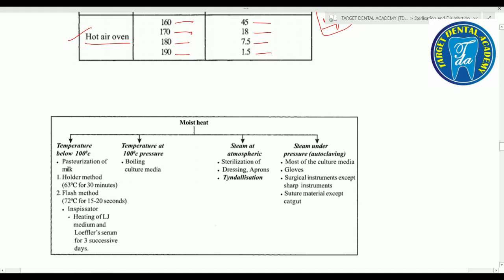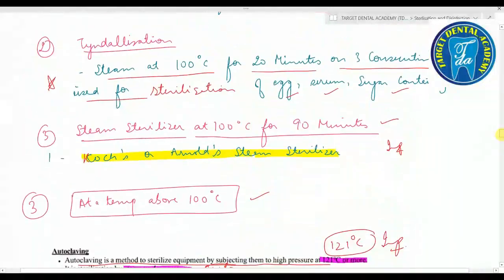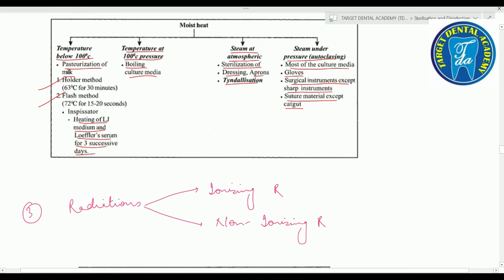Summary of moist heat: below 100°C includes inspissation — heating Lowenstein-Jensen medium and Loeffler serum on three consecutive days. At 100°C includes boiling, culture media, steam at atmospheric pressure for sterilization of dressings and aprons. Above 100°C is autoclaving — steam under pressure — used for most culture media, gloves, surgical instruments except sharp instruments, and suture materials except catgut.